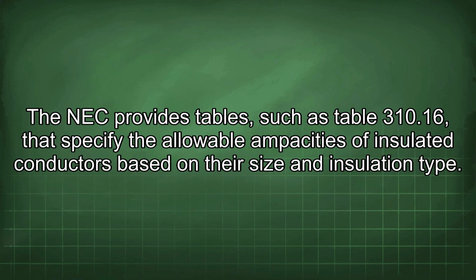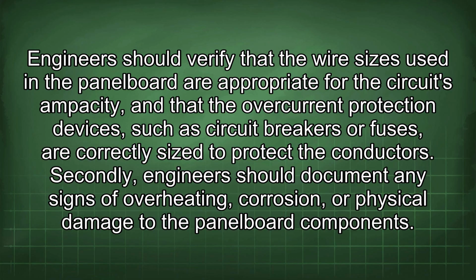The NEC provides tables, such as Table 310.16, that specify the allowable ampacities of insulated conductors based on their size and insulation type. Engineers should verify that the wire sizes used in the panel board are appropriate for the circuit's ampacity and that the overcurrent protection devices, such as circuit breakers or fuses, are correctly sized to protect the conductors.